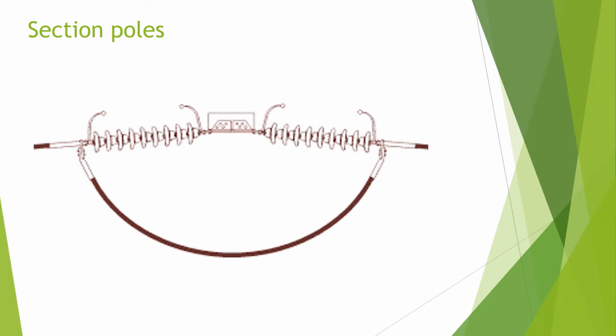Conductor continuity across a section pole is maintained by installing short lengths of conductor which are connected to the line conductors adjacent to the service terminations. These are usually known as jumpers. Jumpers can be defined as being either over or underslung, depending on whether they pass over or under the crossarm. In some areas of the UK, underslung jumpers may be known as loops, while overslung jumpers are also known as bows.